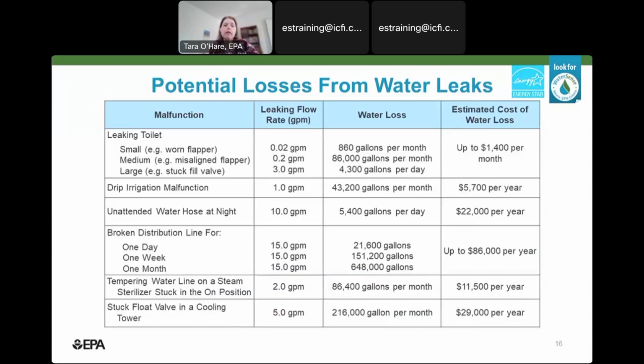So we also put together this chart to give you some more examples. I won't read it, but basically, if you have a leaky toilet, it can be significant. But things like an unattended water hose or a broken distribution line can be really significant because it is so much water that's being used. And even a stuck float valve in a cooling tower is also quite a bit of water use, almost $30,000 per year. So the name of the game is leaks add up quickly, and you want to repair them as fast as possible.